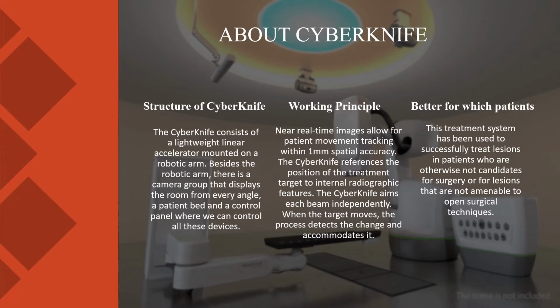Now I will talk about the working principle. Near real-time images allow for tracking the patient's movement within 1 mm spatial accuracy. The Cyberknife references the positions of the treatment target to internal radiographic features such as the skull, bony landmarks, or implanted fiducials rather than a frame. The Cyberknife uses real-time X-rays to establish the position of the lesion during treatment and dynamically brings the radiation beam into alignment with the observed positions of the treatment target. The Cyberknife aims each beam independently. When the target moves, the process detects the change and accommodates it.